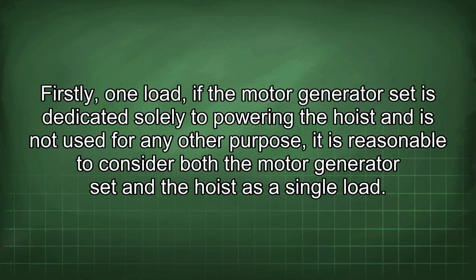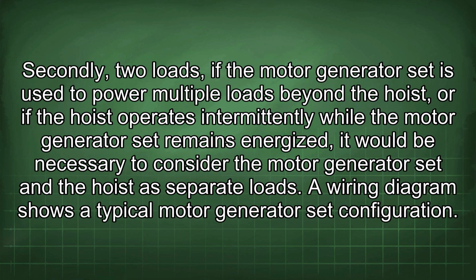If the motor generator set is dedicated solely to powering the hoist and is not used for any other purpose, it is reasonable to consider both the motor generator set and the hoist as a single load. Secondly, two loads. If the motor generator set is used to power multiple loads beyond the hoist, or if the hoist operates intermittently while the motor generator set remains energized, it would be necessary to consider the motor generator set and the hoist as separate loads.